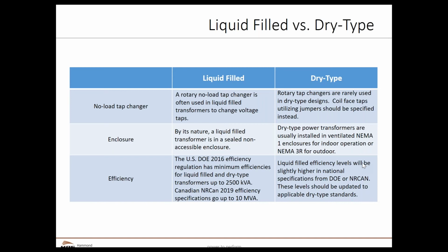Well, in order for us to put contactors in that can do that becomes a very complex and expensive means to do for a dry type transformer. Again, we would just say, change the taps. By its nature, liquid-filled transformers are sealed in a non-accessible, non-ventilated enclosure. Dry type transformers, by their very nature, are ventilated. And again, those ventilation holes provide us with some concerns that the transformer is accessible to the general public.